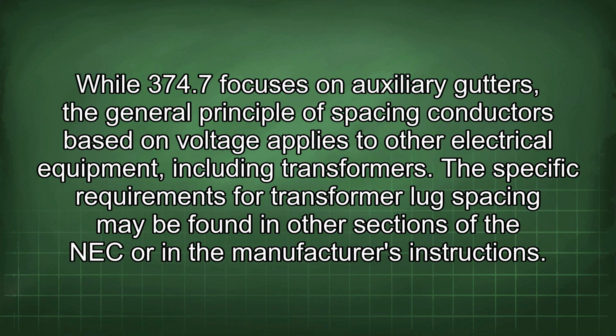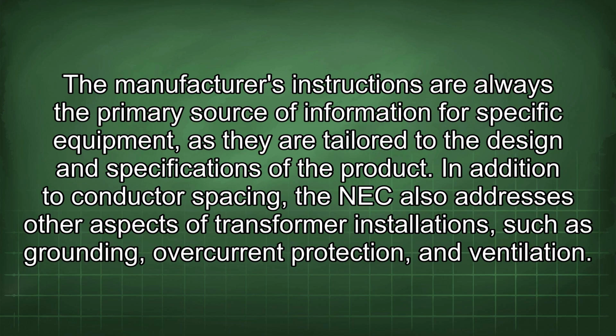While 374.7 focuses on auxiliary gutters, the general principle of spacing conductors based on voltage applies to other electrical equipment, including transformers. The specific requirements for transformer lug spacing may be found in other sections of the NEC or in the manufacturer's instructions. The manufacturer's instructions are always the primary source of information for specific equipment, as they are tailored to the design and specifications of the product.